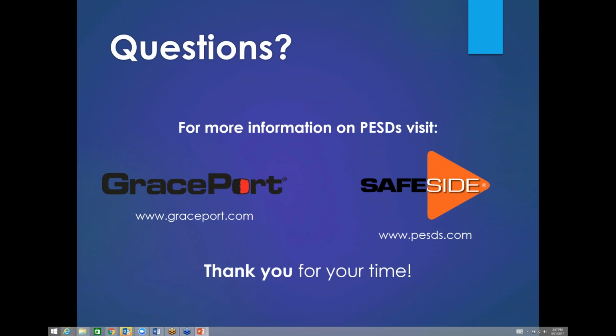So we appreciate that very much. Are the test points safe to be tested with an amp meter? Actually, they're designed to be used with a voltmeter because we've reduced the available current to such a low value. You need to have that testing done with the voltmeter. Yeah, you need to get an ammeter around the wire itself. It wouldn't make sense to try that on the test points.